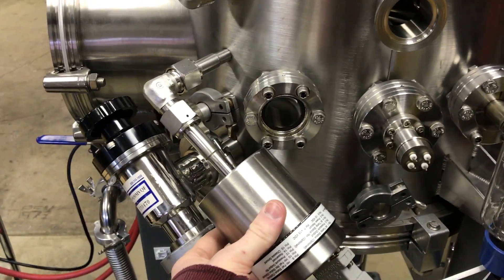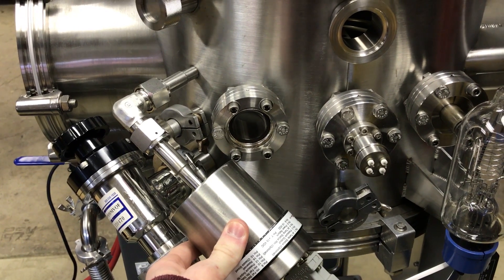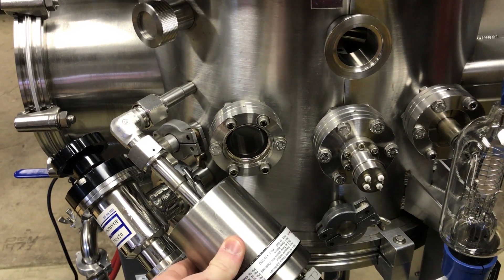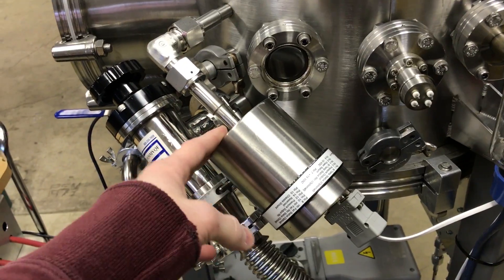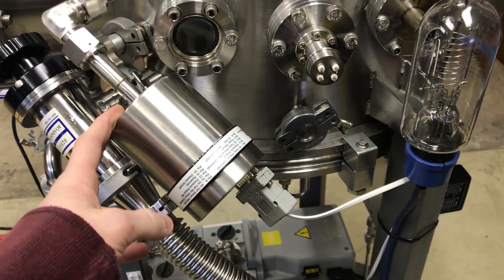But in my case, I'm using this baratron pressure transducer here. This gets me down to 0.001 torr, roughly. It gives me an analog voltage out, and that's pretty simple to use.